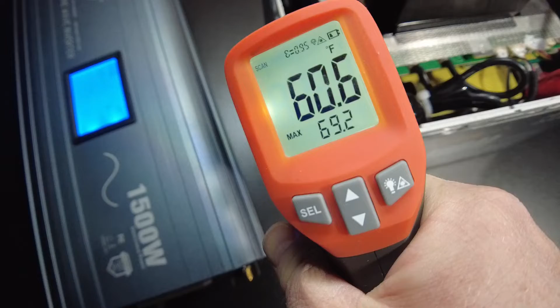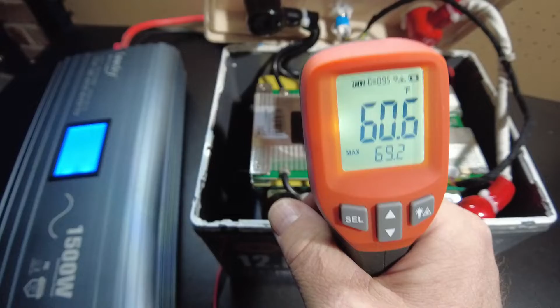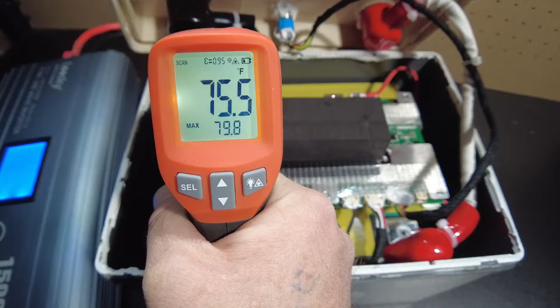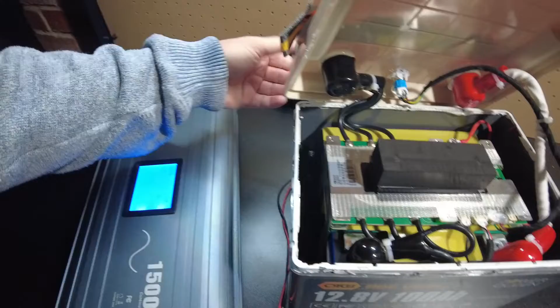The cells are reading around 60 Celsius. I'm sorry, that's not Celsius, that's Fahrenheit. So 78 or 80, 75 Fahrenheit. Not even a problem. Let me show you what this big wire that came with the inverter's doing here. It's at 90, so you can tell that big wire is much warmer than these 3 10 gauge wires.